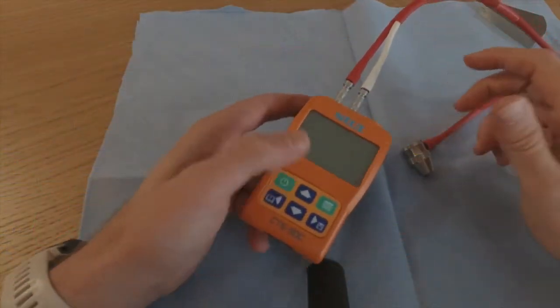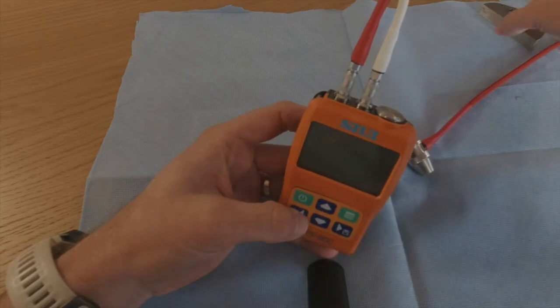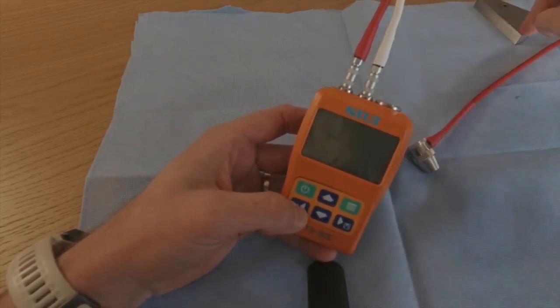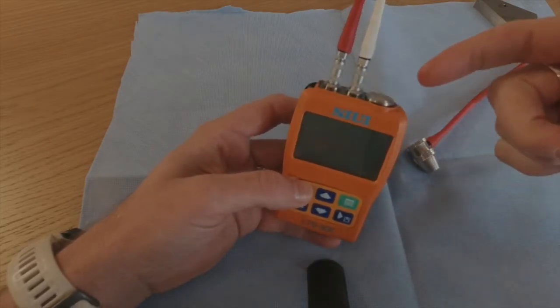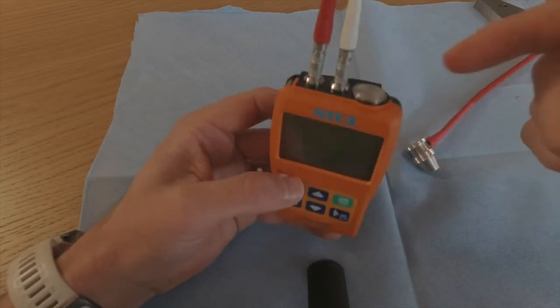One of the things you want to do before you start doing your testing is actually do a self-calibration or verification on a known thickness test piece. What we're going to do now is a simple self-calibration on a 4mm test block which is integrated into the top.